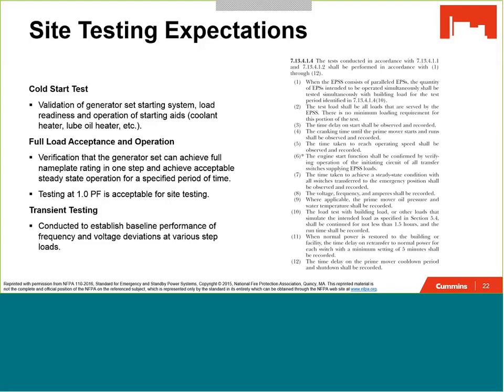Full load acceptance and steady state operation is also fairly common. So we'll see maybe different sets of transient tests, and then full load pickup, and then we'll look at the steady state operation of the product. It is important to note here, this is a question that we get fairly frequently, regarding the power factor that the product should be tested on for on-site testing. The concern here stems from the fact that typically on-site testing, especially commissioning, we see load banks rented instead of using permanently installed load banks.